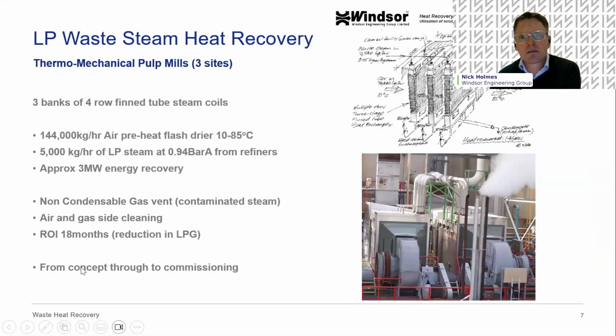Slightly different opportunity here was again in some large pulp mills in New Zealand. There were actually 3 different sites that had the same problem, with low-grade steam being wasted from the refiners. It was contaminated steam, very low pressure, and most of it was being exhausted to atmosphere.